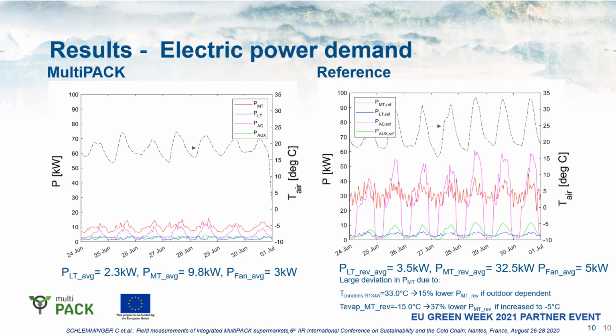By looking at the electric power demand of the system in the dedicated week, we see on the left side here that the MultiPACK system and the reference side have a comparable electric power demand for the low temperature compressors, which is plotted here in blue. There is a small difference in the auxiliary electric power demand, covering, so to say, some pumps and the air cooler, the gas cooler.